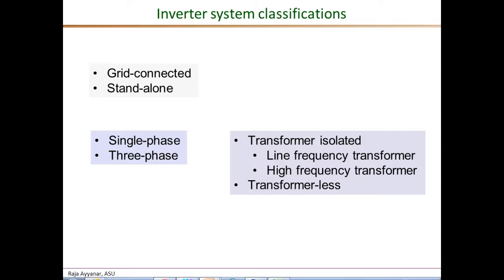String inverters at much lower power levels employ high-frequency transformers, most often in the DC-to-DC conversion stage of the PV inverter. Transformer-less topologies are a more recent phenomenon and have become popular as some of the restrictions on PV array grounding are being relaxed in emerging grid interconnection standards and codes.